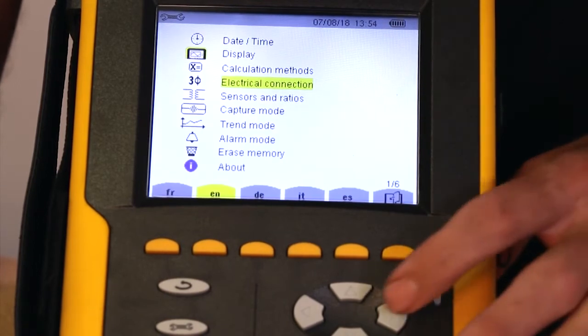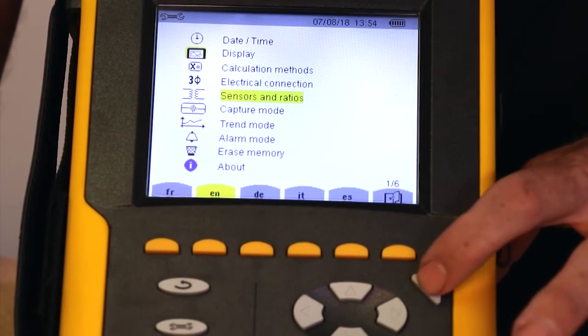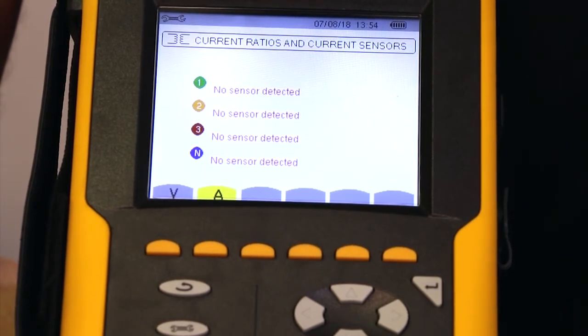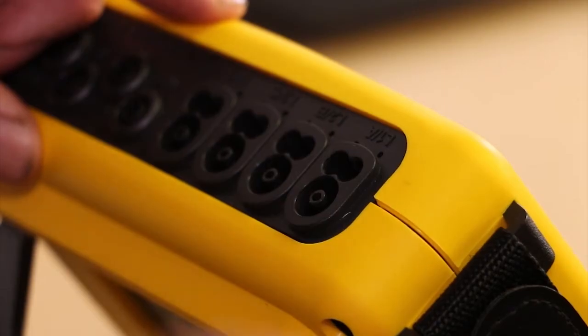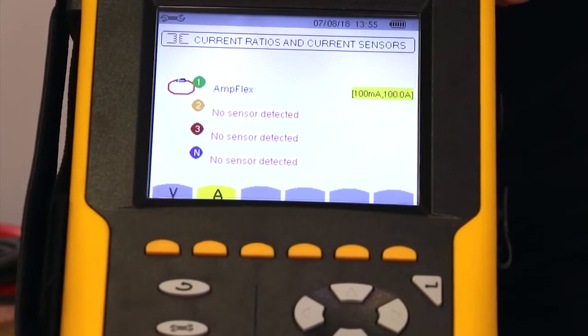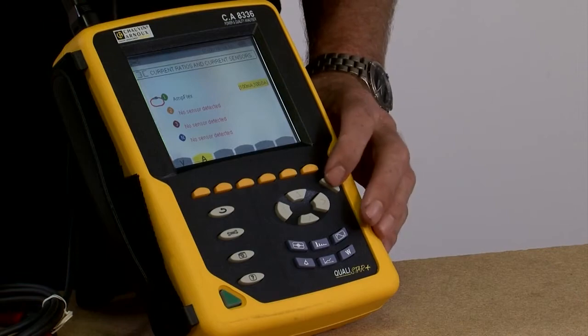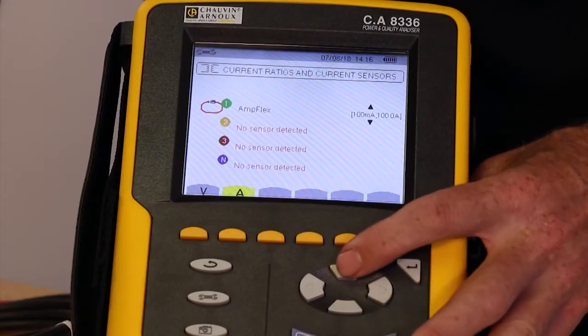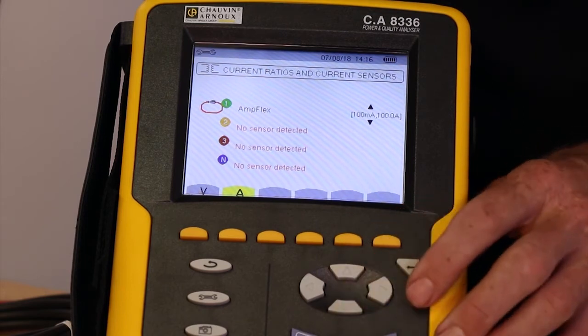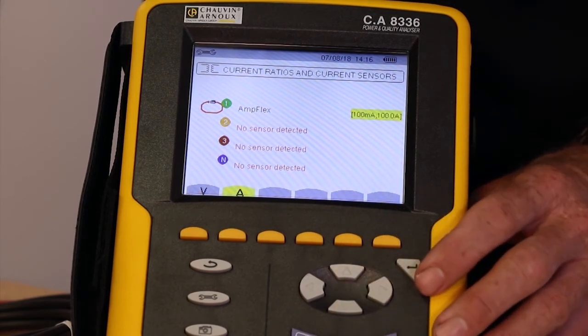Next go to sensors and ratios and press enter. At the moment, no sensors are plugged into the product. As soon as I plug one in, you'll see the Qualistar has detected an AmpFlex Rogowski coil has been connected. While the Qualistar automatically detects what sort of clamp is connected or plugged into it, with some of the clamps, you'll also have the option to change the measurement range.